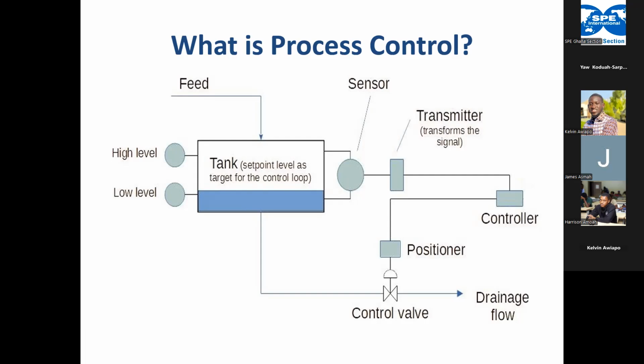So process control is basically regulation of process variables like temperature, pressure, flow rate, and level to maintain a desired operating condition. For instance, I work in a gas industry, and we produce gas for power generation in Ghana. There are set product specifications that the gas has to meet before it leaves the plant. For instance, the temperature, pressure, and even the composition, how much percentage of methane should be there, and how much percentage of nitrogen. The customer will have all those set, so you have to meet those. What process control does is ensure that you're able to meet those product specifications as we send it to the customer.